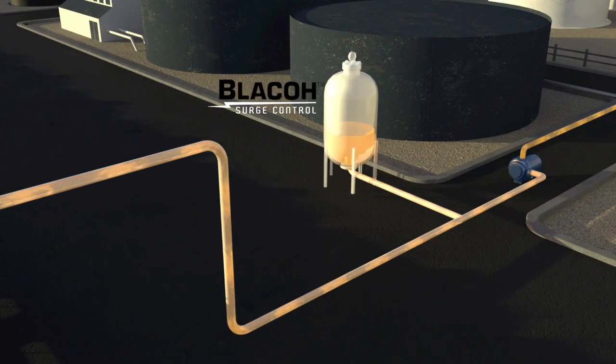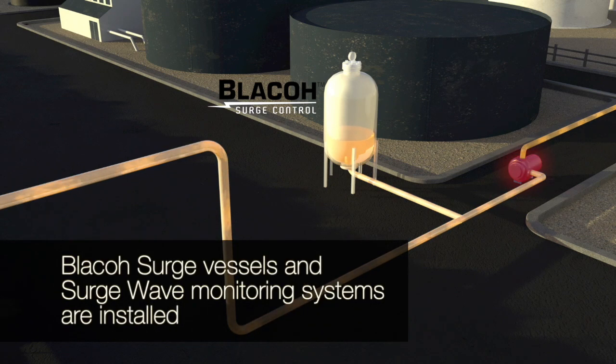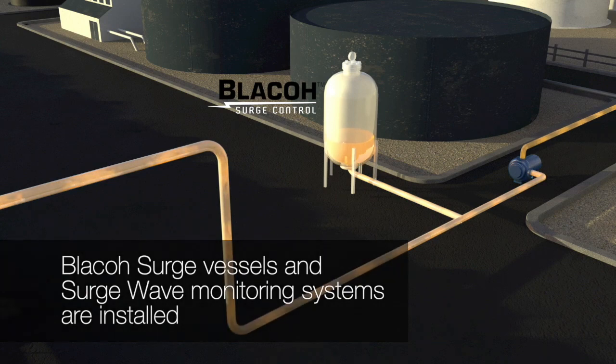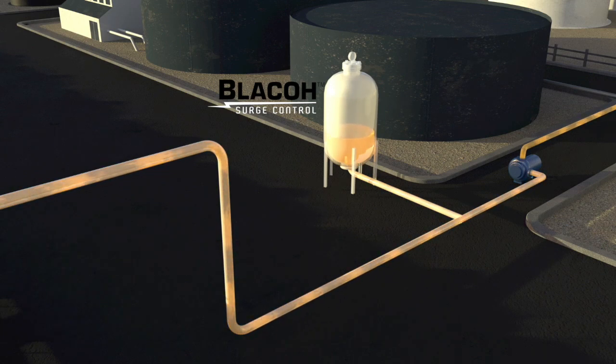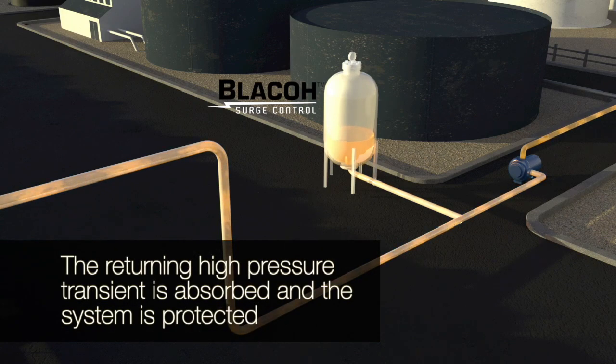When Blacoh surge vessels are installed near the pump discharge and there is a pump trip, fluid is released from the vessel. The added fluid prevents the system from dropping below vapor pressure. The fluid energy caused by the returning high-pressure transient is absorbed by the vessel.